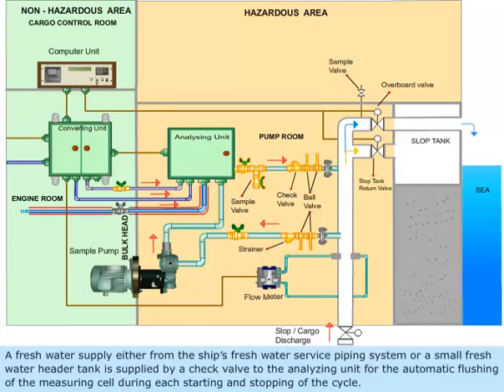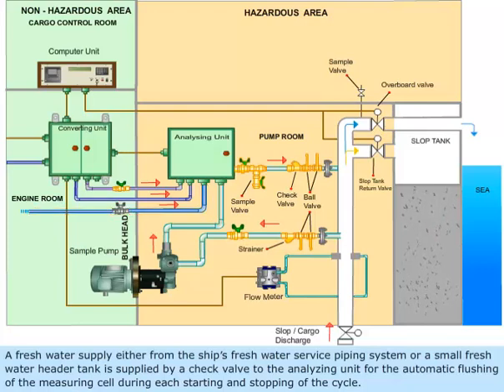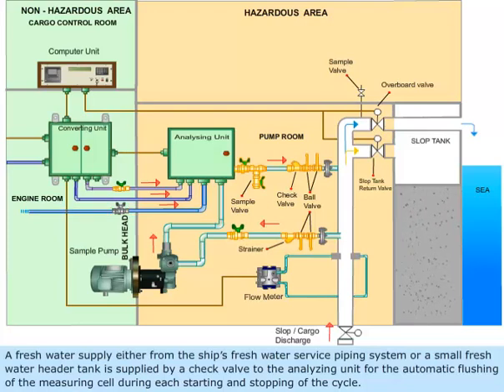Piping for cleaning liquid, flushing water and cable inlets for the intrinsically safe power supply and measuring signals. A fresh water supply, either from the ship's fresh water service piping system or a small fresh water header tank, is supplied by a check valve to the analyzing unit for the automatic flushing of the measuring cell during each starting and stopping of the cycle.